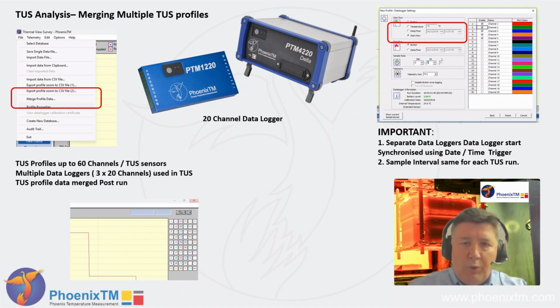A critical requirement if you are to perform multiple data logger runs is obviously to synchronize the data collection process. But within Thermal View Survey, it's possible to start each data logger on the survey at the same point using the date and time trigger, which means that all of the data will be measured at exactly the same point in the survey. So when you merge the data, it will be synchronized perfectly within the software analysis and reporting features.